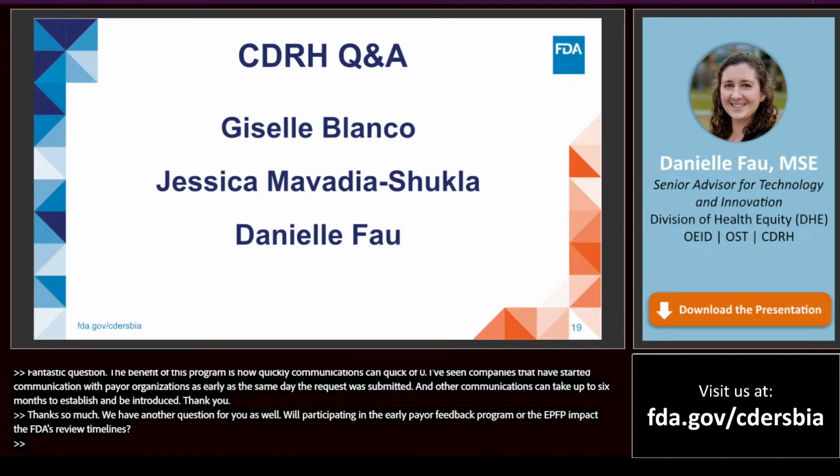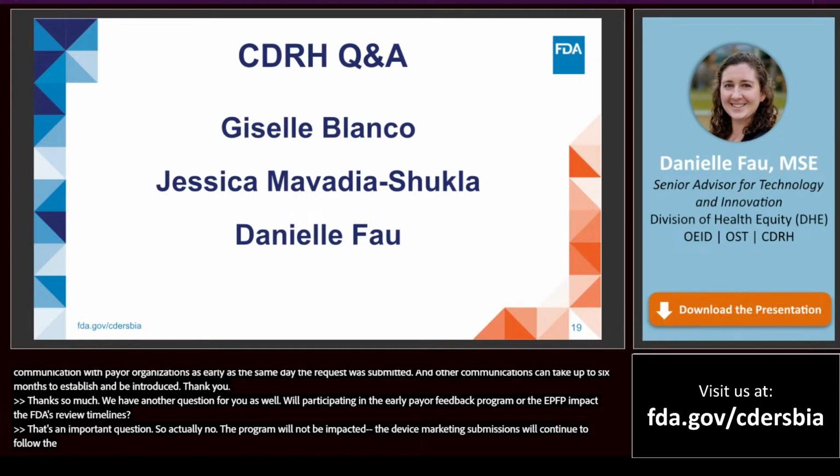Yeah, that's an important question. So actually, no, the program will not be... device marketing submissions will continue to follow the Medical Device User Fee Amendments established review timelines. So participation in the EPFP program does not lengthen or shorten the applicable review clock.